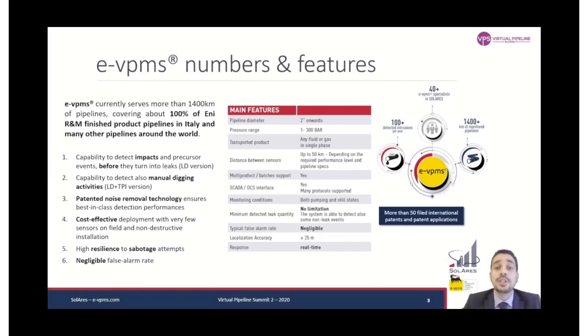The distance between stations will depend on the required performance level and the specifications of the pipeline. It can be up to 50 kilometers in selected cases. We support multi-product batches, full integration with existing equipment. Both pumping and still states are monitored, and we have no limitation on the minimum detected leak quantity. The precision is under 25 meters, but in some cases, we reached also less than 1 meter accuracy.